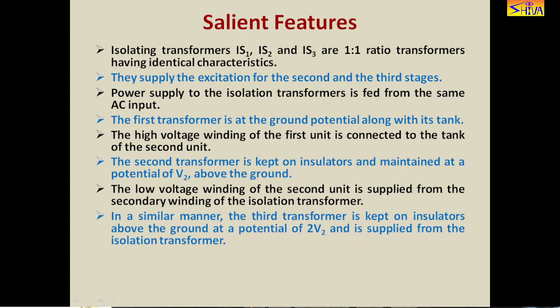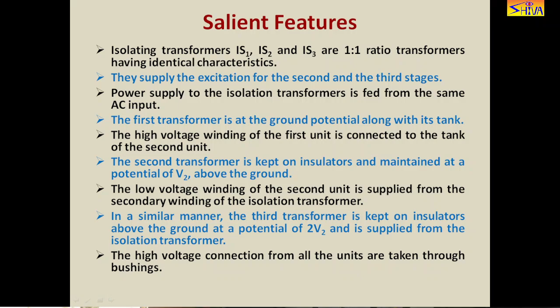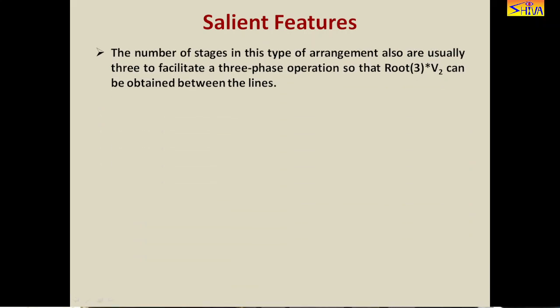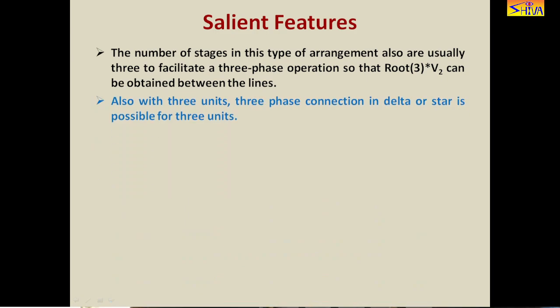Similarly, the third transformer is kept on insulators above ground at a potential of 2V2 and is supplied from the isolation transformer. The high voltage connections from all the units are taken through bushings. The number of stages is usually three to facilitate three-phase operation so that root-3 times V2 can be obtained between the lines as line voltage. With three units, a three-phase connection in delta or star is possible.